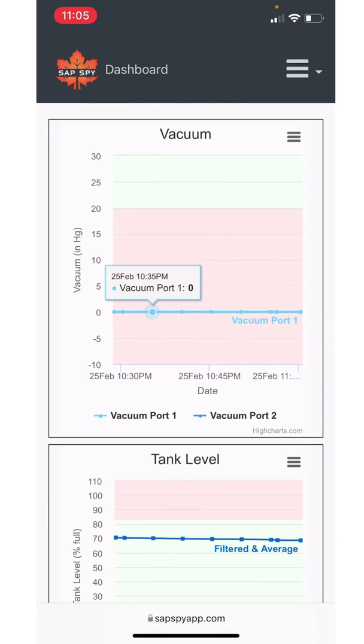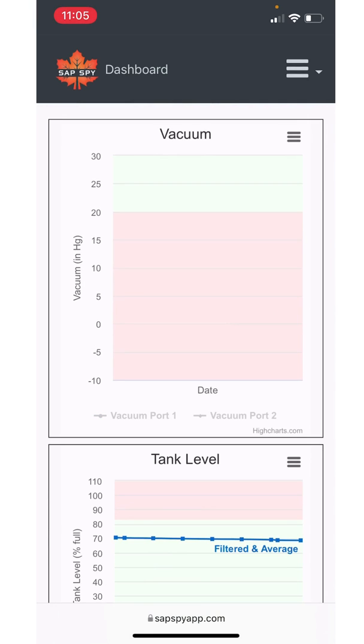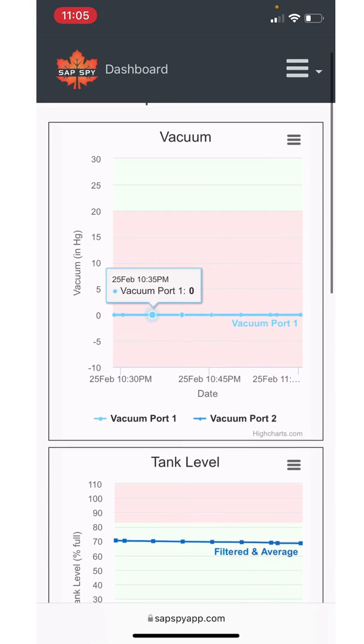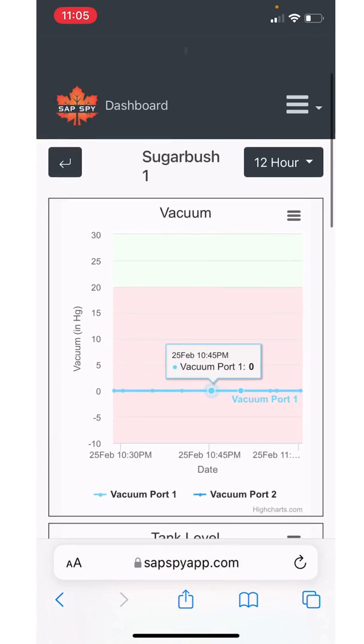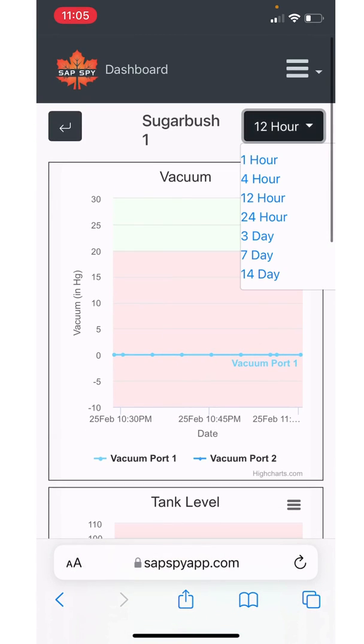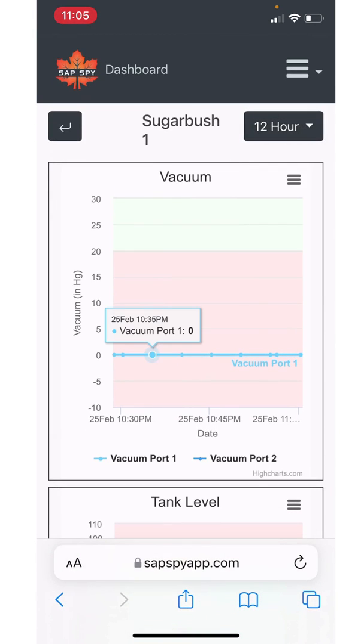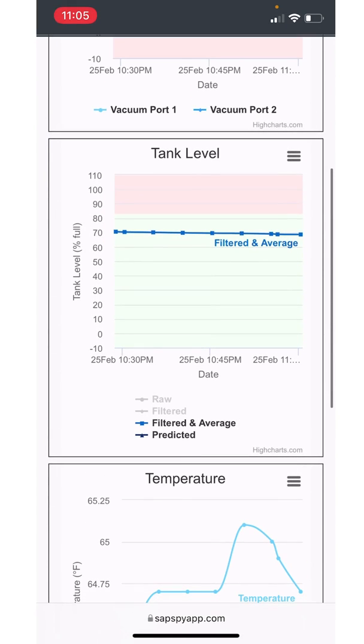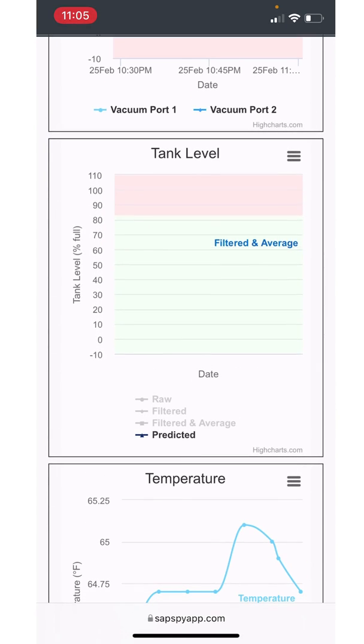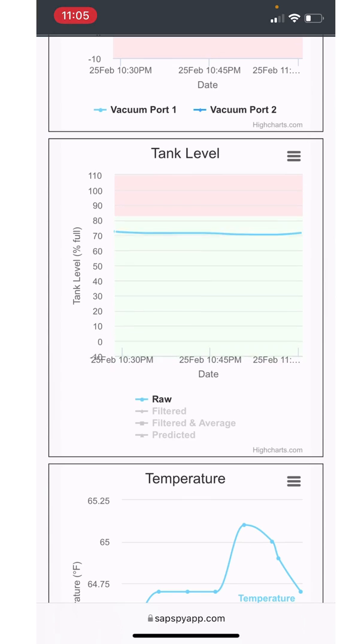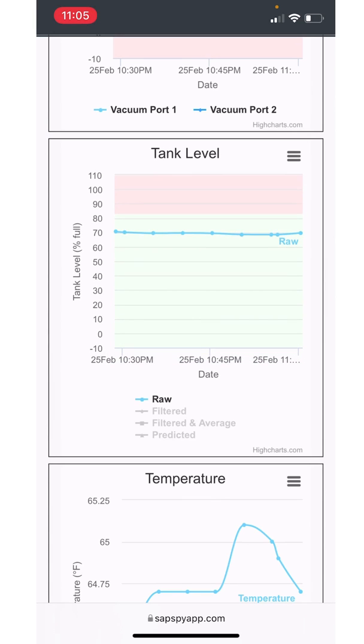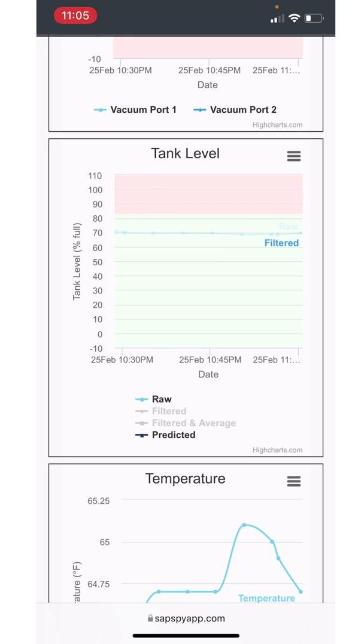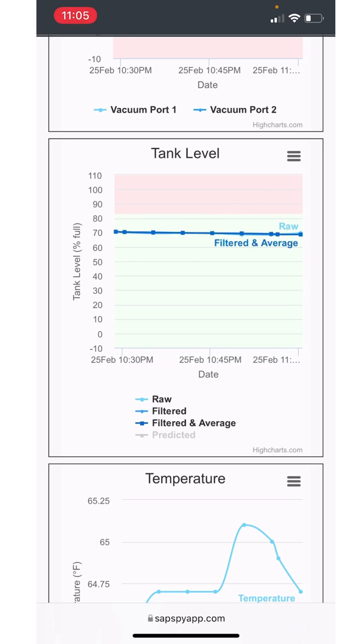If you have maybe a dual port vacuum sensor, I can turn one port and just see one at a time. And I can always change what my display range is up here on the right hand side as well. For tank level, we have a couple different features for tank level. So here in particular, I can see just the raw, which is just the raw data coming from the sensor. I can do a little bit of filtering on that. We can do filtered and average, and then we even can do predicted. Predicted is that future tank level, or what that future tank level will be based on the current rate of change. And you can turn any of those on and off all just by clicking the buttons.